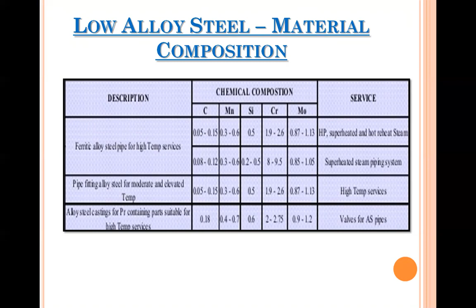Here the chemical compositions are given for these alloy steels and for which services they will be applied. For high pressure, superheated and hot reheat steam, these low alloy steels are used. Ferritic alloy steel pipe for high temperature services is used. For valves, these alloy steel castings are used. And the chemical composition given is the carbon percentage, manganese, silicon percentage, chromium percentage, they have mentioned for this particular service and application.